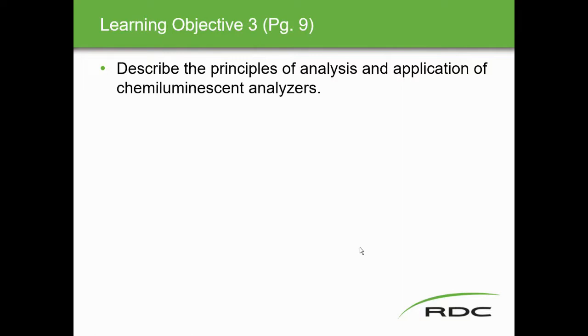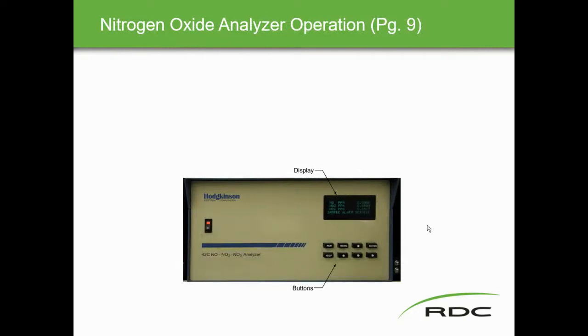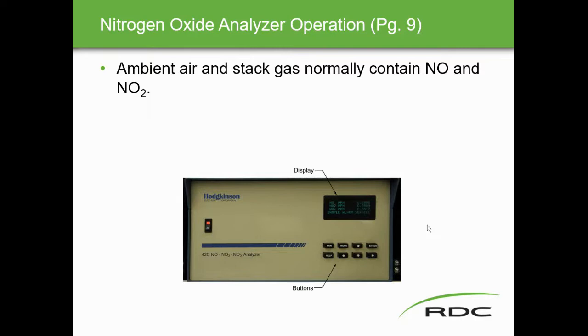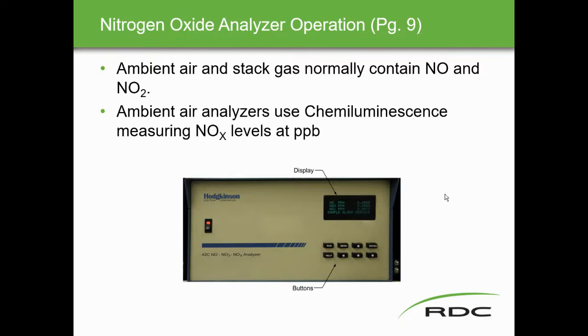Learning objective three: describe the principles of analysis and application of chemiluminescent analyzers. Stack gas normally contains both NO and NO2 from combustion. Ambient air analyzers use chemiluminescence to measure NOx levels at parts per billion. By contrast, UV analyzers measure stack gas NO2 at parts per million — chemiluminescence gives us the much lower detection range needed for ambient monitoring.